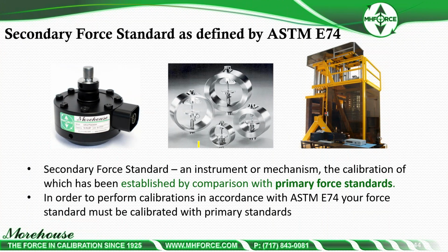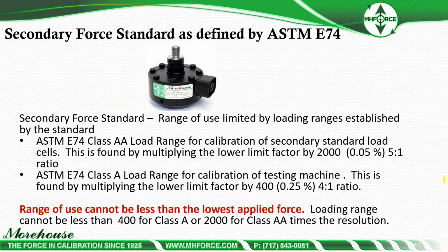So secondary force standard, those are the standards. There's some examples. Instrument or mechanism of calibration which has been established by comparison with primary standards. You have load cells, proving rings, and then you have lever amplification machines. In order to perform calibrations in accordance with ASTM E74, your force standard must be calibrated with primary standards. So secondary standard as defined is class AA loading range for calibration is 2,000 times the lower limit factor, which gives a 5-to-1 ratio. And then those devices or dead weights can be used to assign a class A loading range, which gives a 4-to-1 ratio on the testing machine.